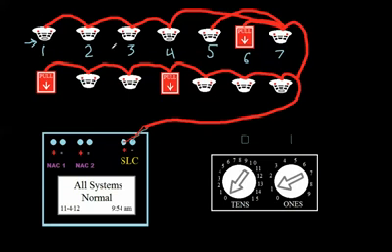Now once I pick the addresses in the field, I have to go into the panel's program and tell it, okay, device 1 is a heat detector, device 2 is a smoke detector, and so on and so on. And the panel is going to use this data communication to always check in with it. And that's the reason that I can just, as I said before, T-tap wherever I want, because as long as this is connected, the panel doesn't care what order it's wired in. At least again on a Notifier and a Fire-Lite, it doesn't care what order it's wired in. As long as they're all on this loop somewhere, it's going to poll all the devices that I tell it should be there. So let's say I skipped device 3. I never told it that smoke detector 3 existed.